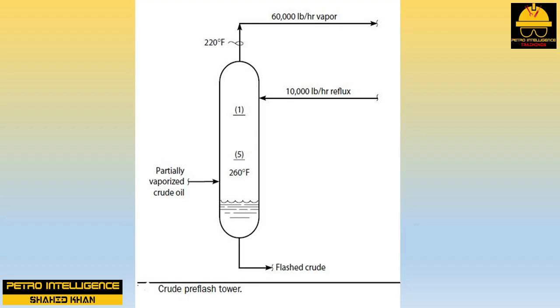Internal reflux evaporation: the tray temperatures in our pre-flash tower drop as the gas flows up the tower. Most of the reduced sensible heat content of the flowing gas is converted to latent heat of evaporation of the downflowing reflux. This means that the liquid flow (internal reflux rate) decreases as the liquid flows down the column. The greater the temperature drop per tray, the greater the evaporation of internal reflux. It is not unusual for 80 to 90% of the reflux to evaporate between the top and bottom trays in the absorption section of many towers. We say the lower trays in the absorption section are drying out. The separation efficiency of trays operating with extremely low liquid flows over their weirs will be very low — this problem is commonly encountered for towers with low reflux ratios and a multi-component overhead product composition.